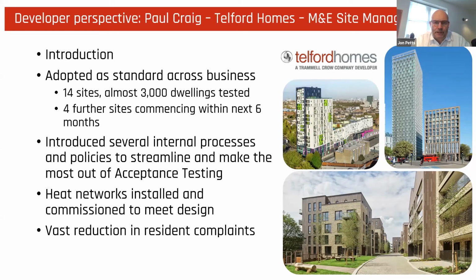As you probably picked up on some of the other discussions throughout the day, it only needs a small amount of bypass on an HIU for the network to go down, and otherwise all the commissioning within the flat is picking up loads of little details which collectively, individually may be quite small, but they do all have a knock-on effect to the wider network.